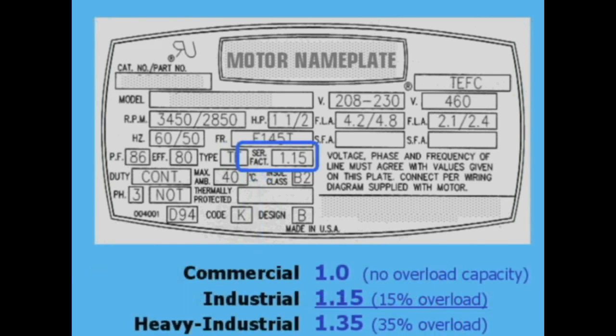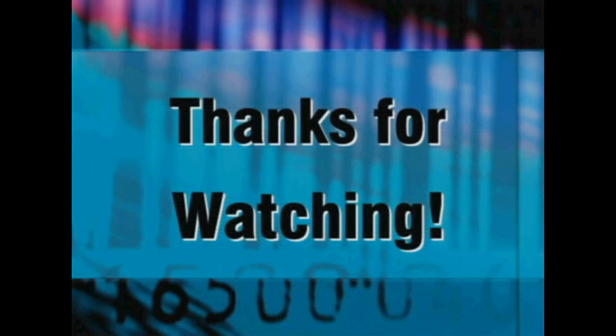Less expensive commercial grade motors are often rated 1.0 with no overload capacity. Industrial motors cost slightly more but are usually rated 1.15, meaning they're able to deliver 15% more than rated horsepower indefinitely.